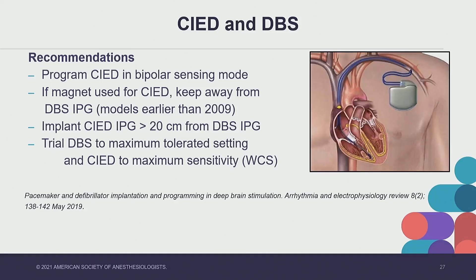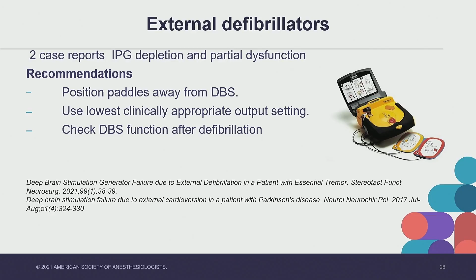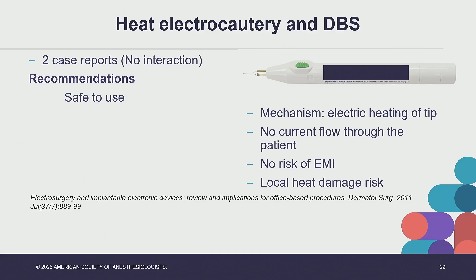External defibrillators: there have been 2 case reports of IPG depletion and partial dysfunction. Again, the recommendations are to position paddles away from the DBS, use the lowest clinically appropriate output setting, and check DBS function after defibrillation. Now, there are 2 types of electrocautery. The one that we use in the operating room is the electrosurgical unit, but this is a heat electrocautery which dermatologists use all the time. This is a handheld cautery in which there is no electrical current that goes to the patient. There is a filament, like in an electrical bulb, and that gets heated up. There is no risk of EMI, but there is a risk if you are placing it near the IPG of the DBS, which can cause heat damage.